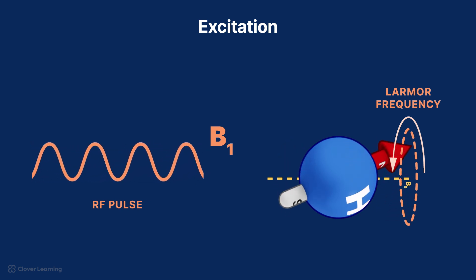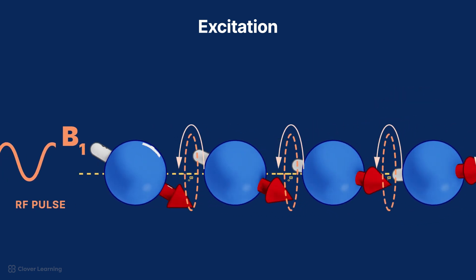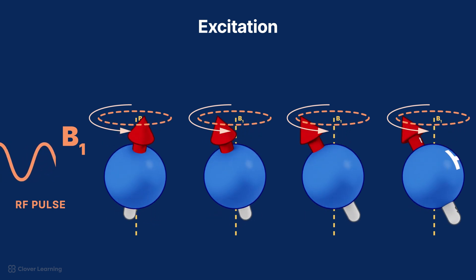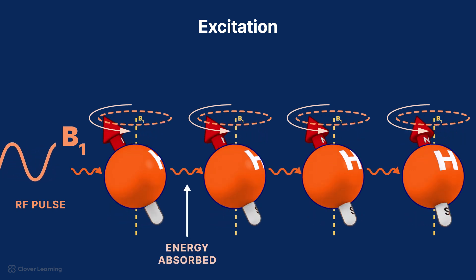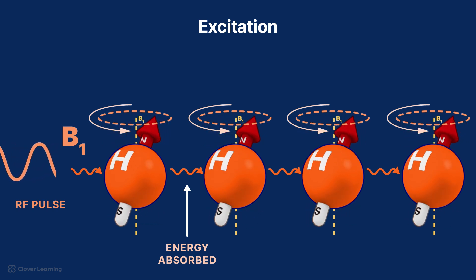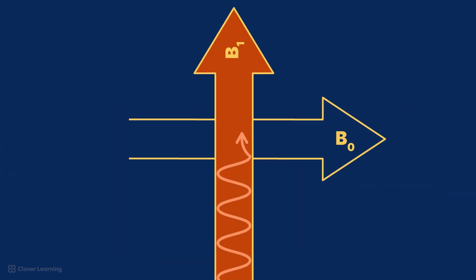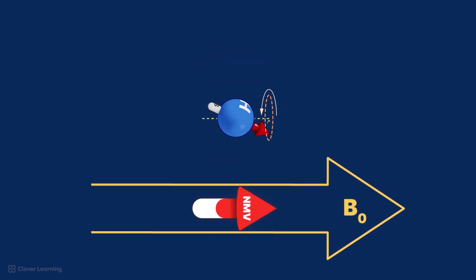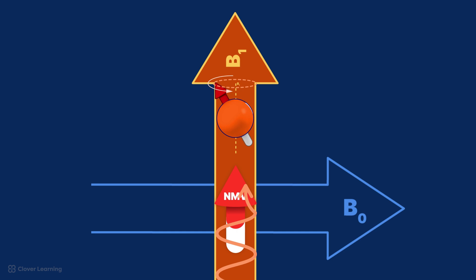We refer to this RF excitation pulse as B sub 1. The energy from the RF pulse temporarily disrupts the alignment of the hydrogen nuclei with the magnetic field, B sub 0. The energy is absorbed by the hydrogen nuclei and causes the magnetic moments of the hydrogen nuclei to precess in phase, or in sync, with one another. The RF excitation pulse comes in at a 90-degree angle to the longitudinal plane and B sub 0. When only exposed to B sub 0, the net magnetic vector, or NMV, is in alignment with the longitudinal plane. When the RF excitation pulse excites the NMV at a 90-degree angle, it is tilted or flipped into the transverse plane.